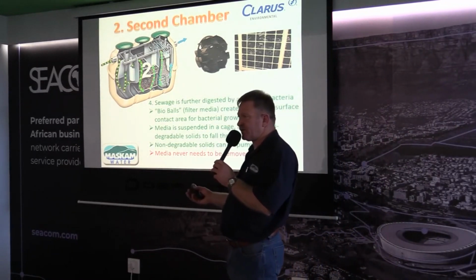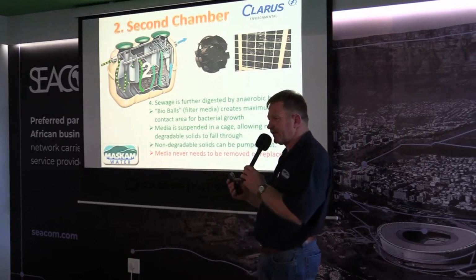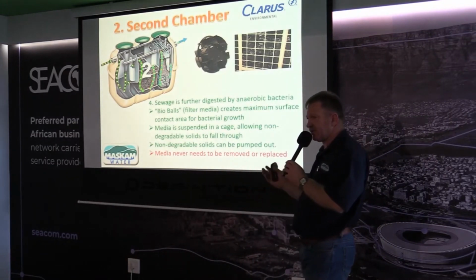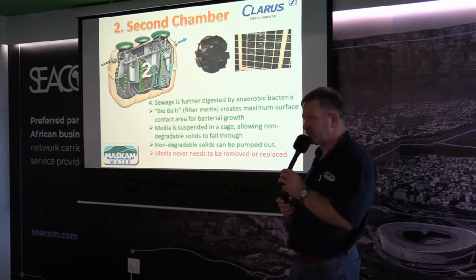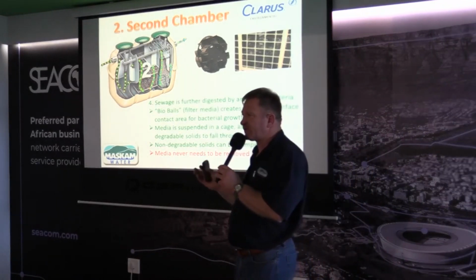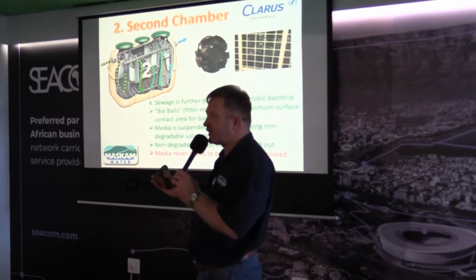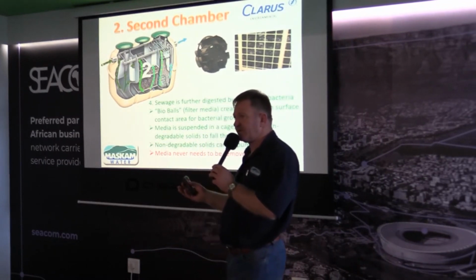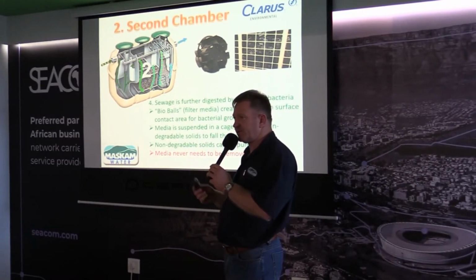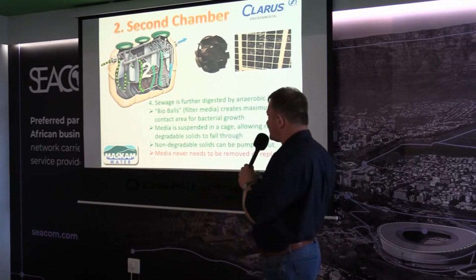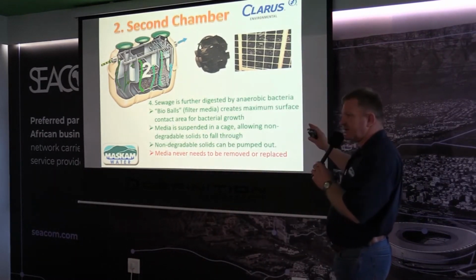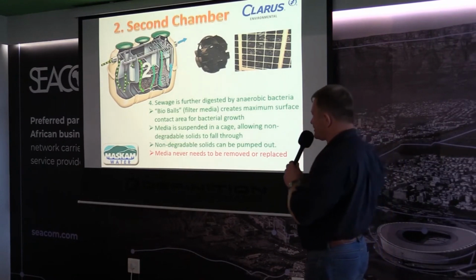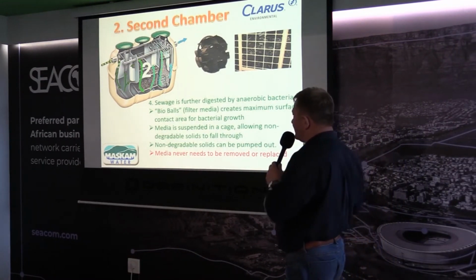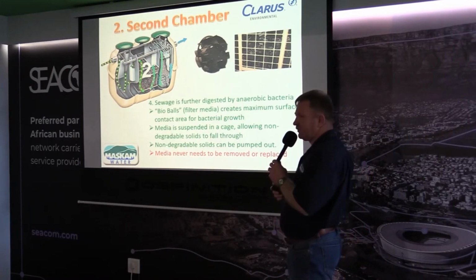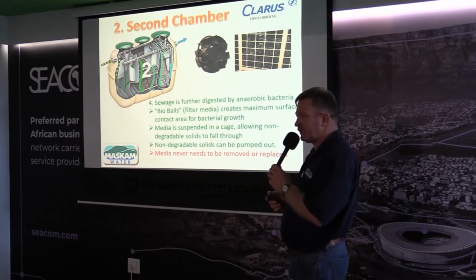How do you know when to desludge it? That's part of the servicing, is to measure the sludge depth, and the sludge depth at the time of servicing will tell you whether it is necessary to remove sludge or not. Typically we find desludging between 4 and 6 years. We get some abusive situations where it needs to be done more often, and we get some cases, especially where seasonal occupation is, that we go up to 10 years without desludging. So there is no fixed time period. The sludge depth test during the servicing will tell you whether that's necessary. But these balls cannot be removed once the system is fully assembled.